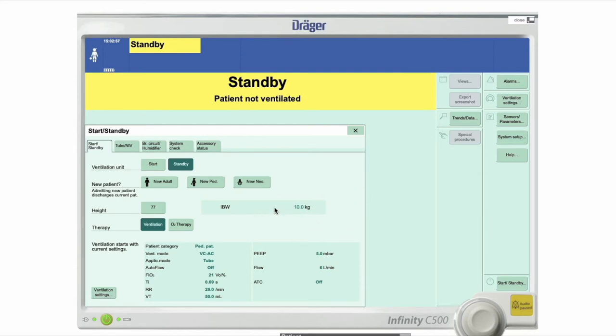But the weight does need to be put in, because if you put the weight in at the beginning, the ventilating settings and the alarm limits are then set up in the background for a child of that weight. If you don't put the weight in, you're not really getting anything much, or you would have forgot. There's always some sort of number in there, and you won't get the correct vent settings or the alarm limits to start. So it's really important that you put it in.